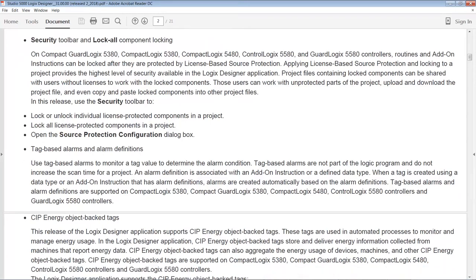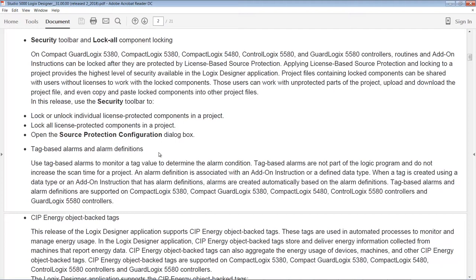You can see some additional things here: tag-based alarms and alarm definitions. These are very cool as they added the ability to add thousands of tag-based alarms and definitions in the controller on the 5x80 products. We couldn't do that with instruction-based alarms because they use a lot of horsepower and memory. But now with these new tag-based alarms and alarm definitions, it doesn't really burden the processor or the core that's running your code. It uses a separate core, so it has nearly zero impact on your scan time and gives you the ability to add alarm definitions to pretty much anything in your tag database. Very cool, and I'm looking forward to trying this out.